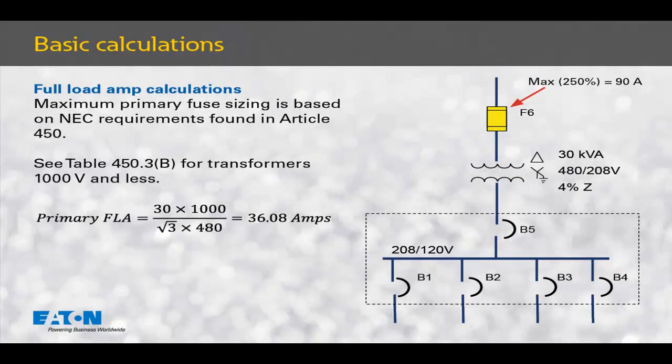The primary full-load amps of the transformer is needed to determine the maximum size fuse for transformer primary protection. The primary full-load amps is calculated as 36.08 amps at 480 volts. We use Table 450.3b of the National Electrical Code to determine the maximum fuse size for the primary main fuse, F6. The maximum size of the primary fuse is calculated by multiplying 36.08 amps by 2.5, giving us 90 amps as our maximum fuse size.